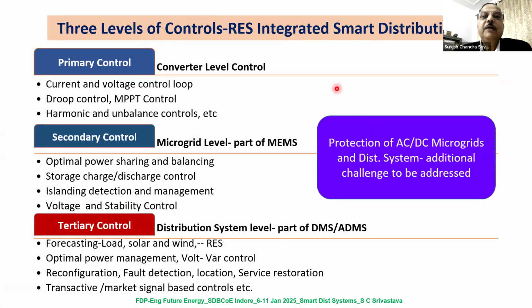Now, with these changes taking place in a smart distribution system being conceived, where renewables are being integrated, 3 levels of controls are required. One is at converter level. So every converter which interfaces to either storage or to renewable should have voltage and current control loop, maximum power point tracking because you want to extract maximum power from renewable sources, droop control if they are sharing power, harmonic and unbalanced control. If you have microgrids, then at microgrid level, you need optimal sharing. If you have more than one source or even battery, you want to optimally share with the PV for balancing purpose. Storage, optimal charge discharge control is required.